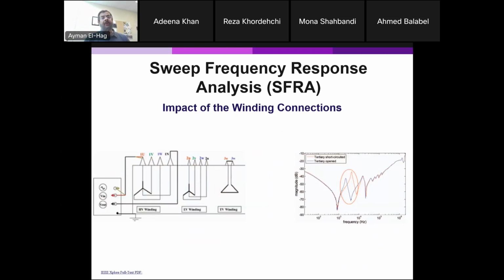Another issue, also, when you do the fingerprint of your transformer, you have to make sure what the connection of the transformer was. Very, very important. For example, here, we are taking the signature applying to the high voltage, and we're receiving it from the neutral. Okay, so that is our system. Here we have the low voltage open circuit, and we have the tertiary winding short circuited. Now, if I forgot this condition and just open circuit the tertiary windings, you will see here a huge difference. This is the middle region, the interaction between the windings. Because I changed the connection of the winding, there's a huge difference between the two.